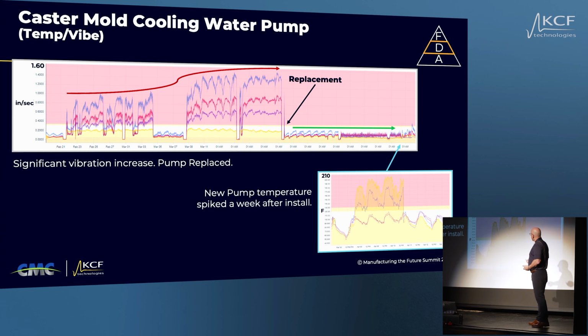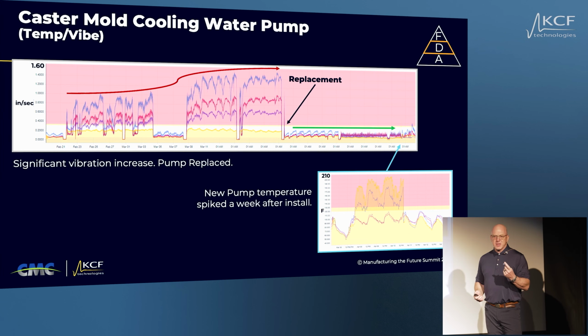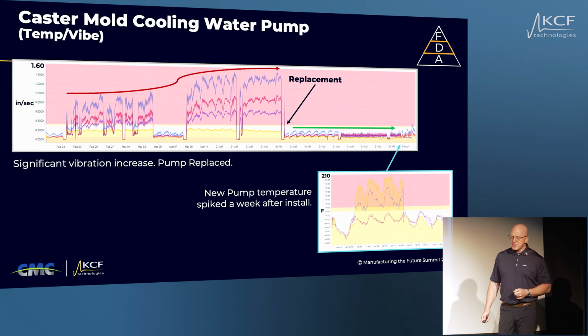And there's the trend. We were actually running at 200 F. We sent a shift electrician out Friday afternoon, spot temp checked the motor, and it was 200 F. So we had to modify the program so that we could run both pumps at the same time to allow us to bumplessly shut the bad one off, which we managed to do without interrupting cast.